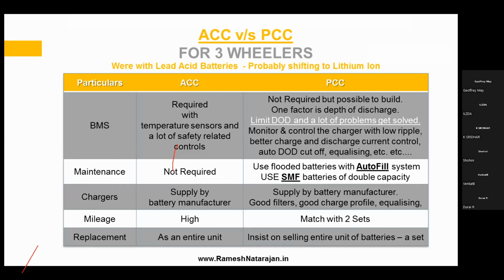Another thing the BMS has to do is monitor and control the charger and ensure that a low ripple goes in, a better charge and discharge current control is there, the auto DOD cutoff is there, and equalizing is possible. If this BMS does that, and there is no need of a temperature sensor and a lot of other safety related controls, if the depth of discharge is limited, lead acid battery will definitely perform well in cycling application.